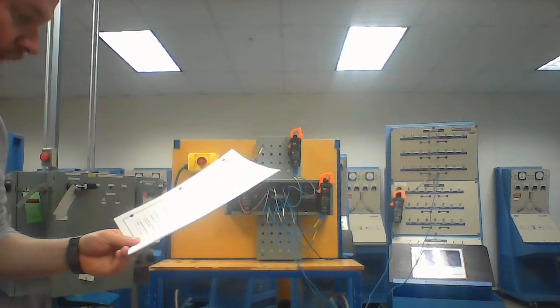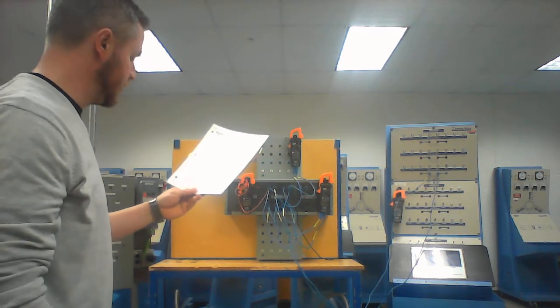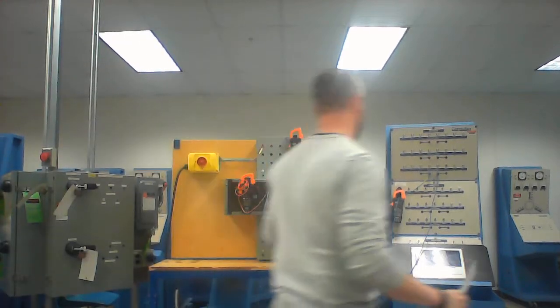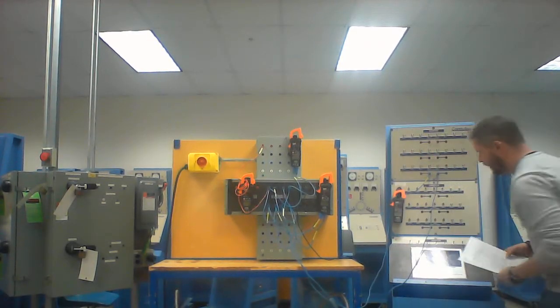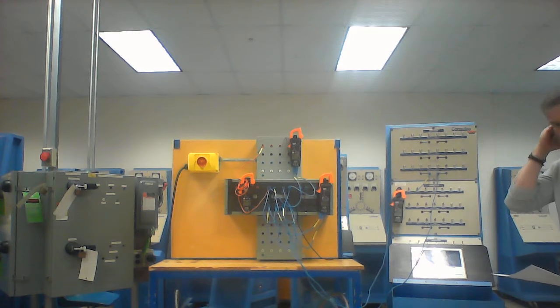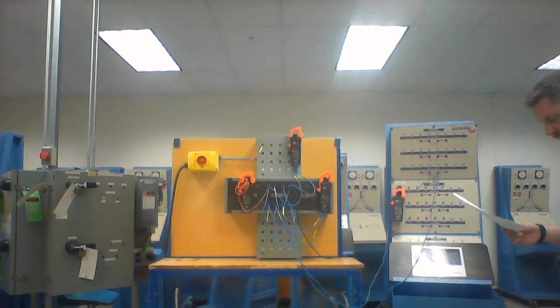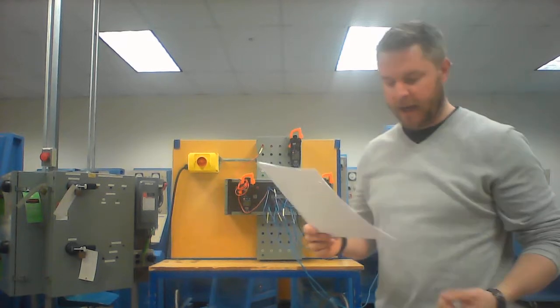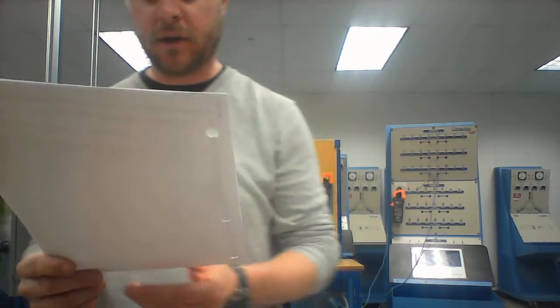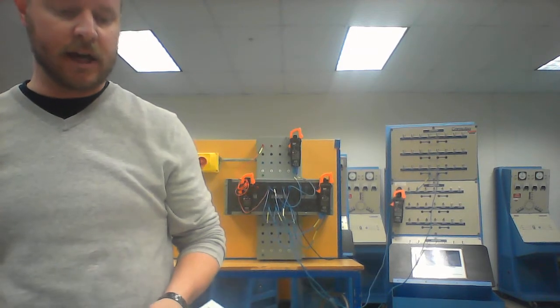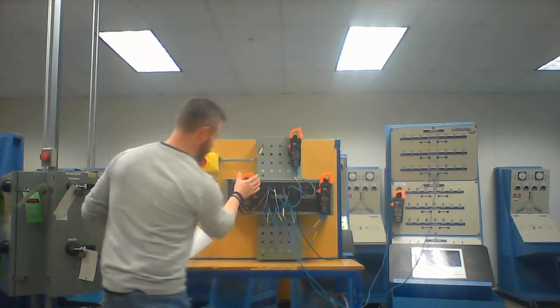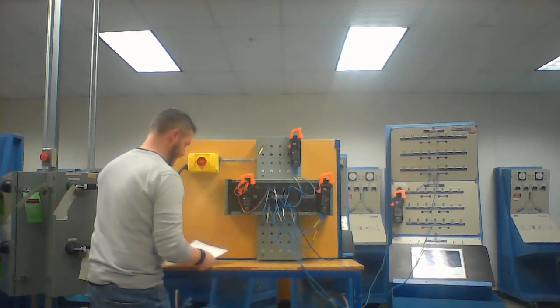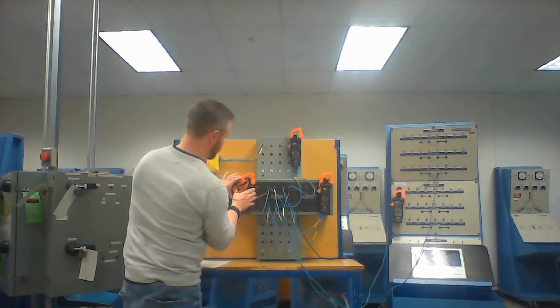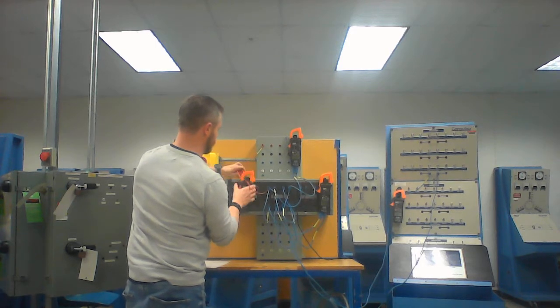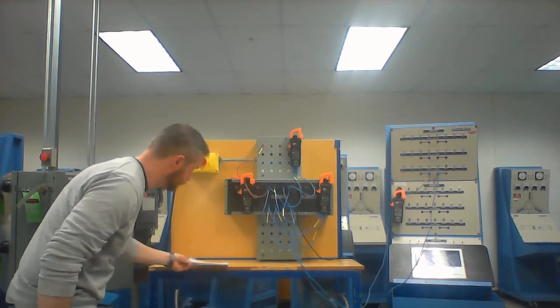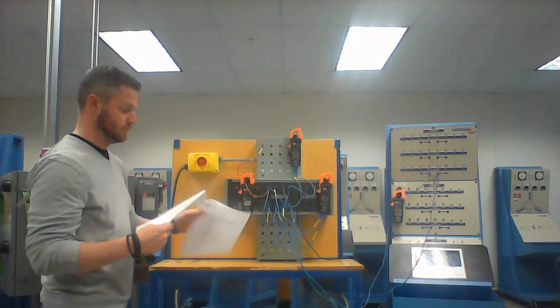So turn the power on, and using the clamp-on meter, measure the current flow in the secondary circuit of the transformer in amperes. That's coming over here. I have 0.52 amps of current flow. Then I go through and look at step number 9, and I calculate the amount of primary current using the voltage ratio. Don't forget to add in the excitation current. Your excitation current was that 6-turn coil over here before. So Mr. Mankulich will do that calculation, and then I will tell you what the next step is when I look at the actual current flow.